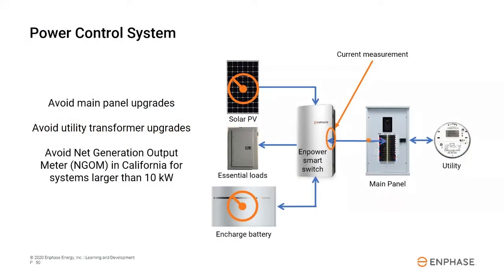And there are two additional benefits of PCS. The other benefit is that it can avoid utility transformer upgrades by limiting power exported to the grid to the power of the PV system alone. So there are some circumstances I've heard, especially on the East Coast, where utilities will actually ask customers to foot the bill to upgrade a transformer just for the sake of installing PV and storage. So with PCS, if the AHJ approves the use of it, then you can, again, limit the current and avoid that transformer upgrade.